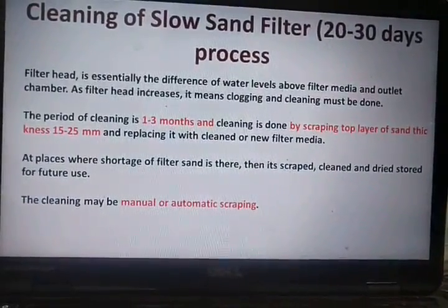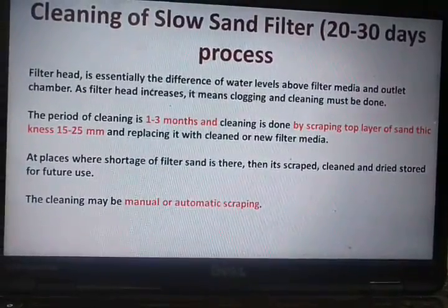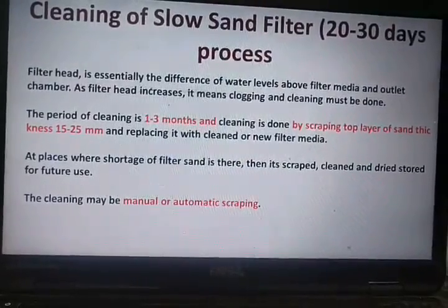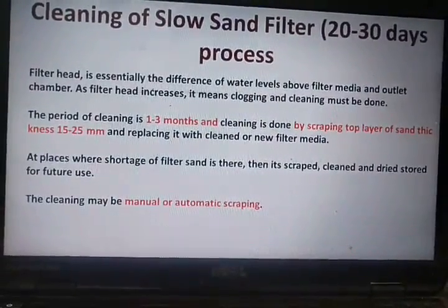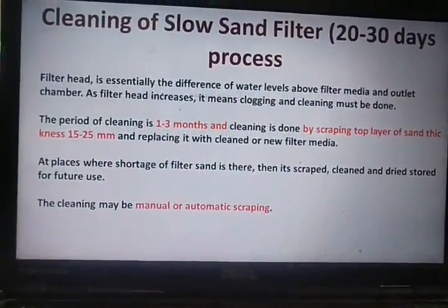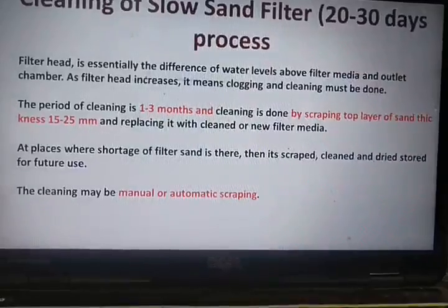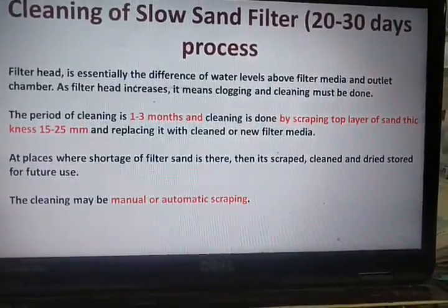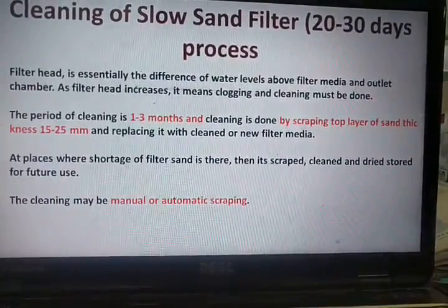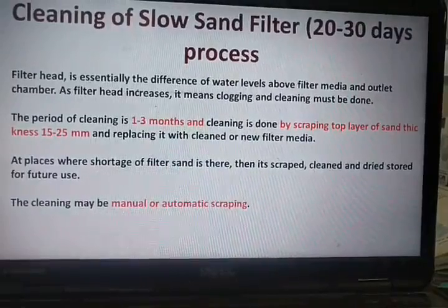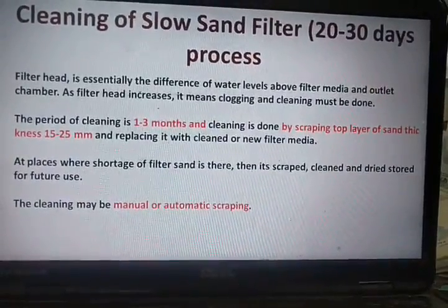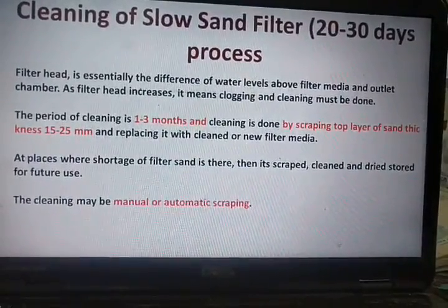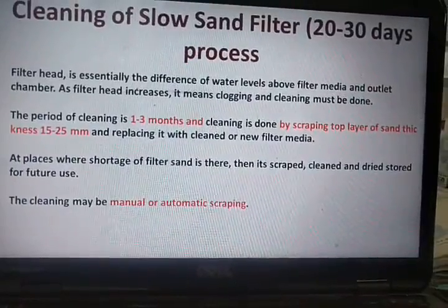That is, the scraping or removing of the top layer of the sand is done. That is, the top layers of around 15 to 25 mm is replaced, and it is cleaned with new filter media, okay. In case you don't find the sand in those types of areas, the sand which is removed, the 15 to 25 mm of the top layer that is scraped, is cleaned, dried, and again stored for future usage.